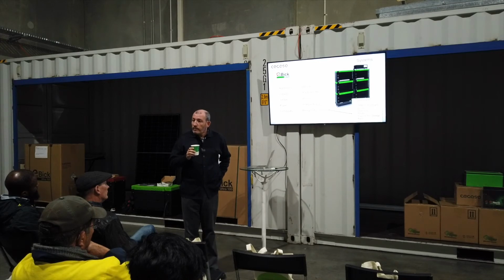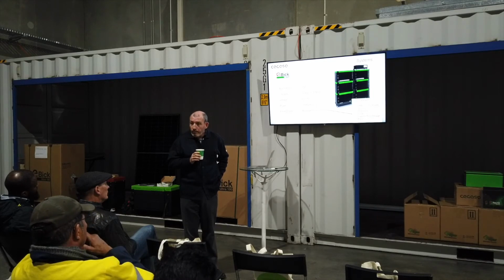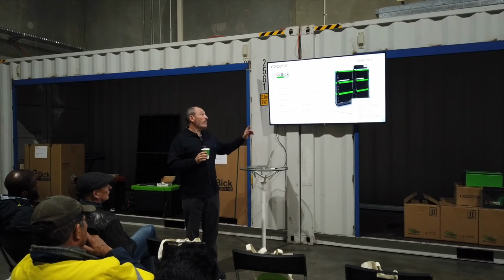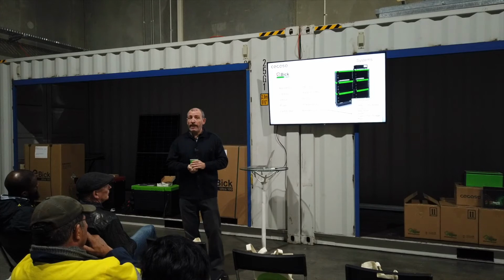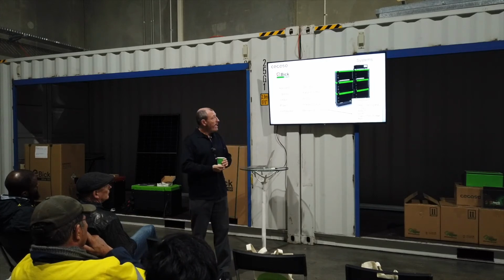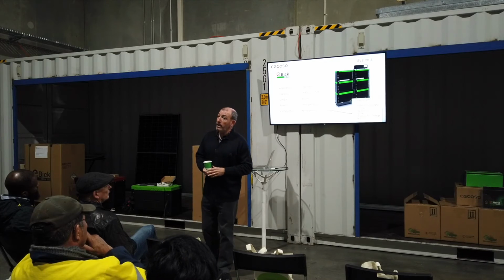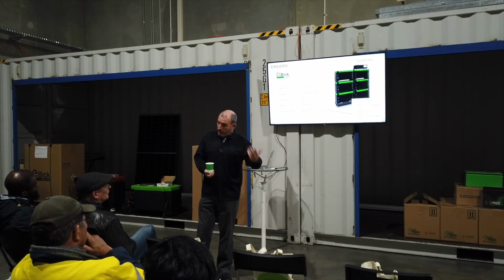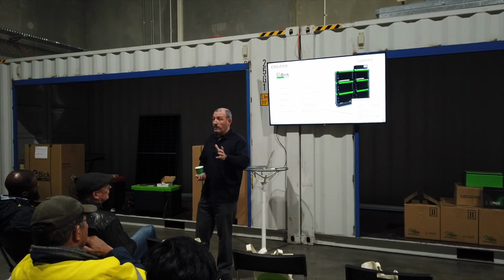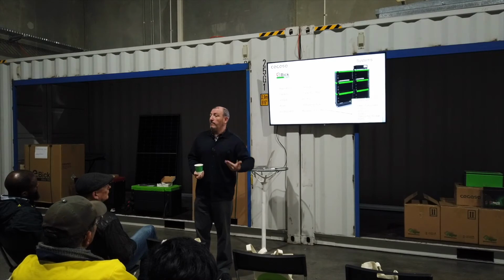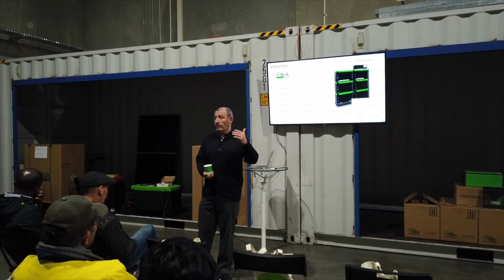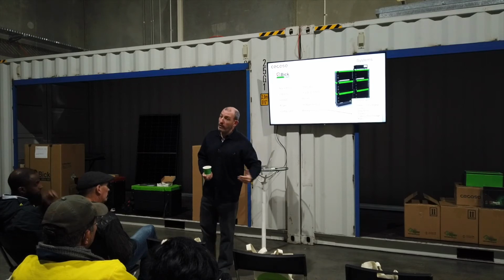Question: before you said when you have an unmanaged unit, you set it up as lead acid battery with set values. When we do a managed setting, are you not really using the lithium settings? Well, in the managed setting, you're absolutely right, but it's not so manual. With most inverters, having passed the integration, we're already an option in the menu, so it presets most of the stuff. You might change some values according to the application, but that's part of the integration - you don't need to bother about the small details because they're already in the setup.